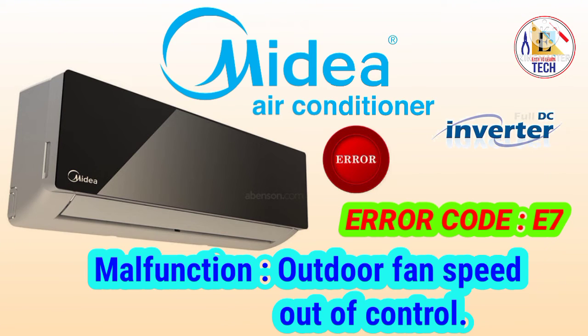When you see the error E7, it means your outdoor fan speed is out of control. First of all, you have to check for obstruction in your outdoor fan. If there is no obstruction, then you have to check if the outdoor fan motor is good or not. You have to check the resistance of your outdoor fan motor. If the resistance is not good, you can change the outdoor fan motor and you will get the solution.